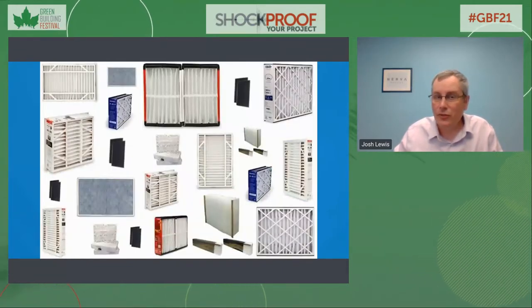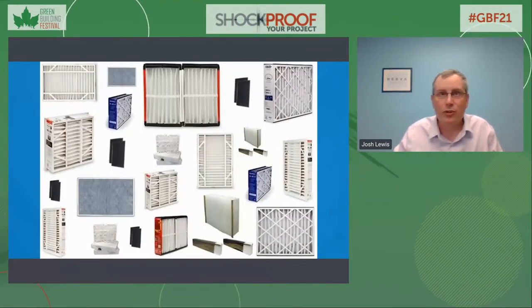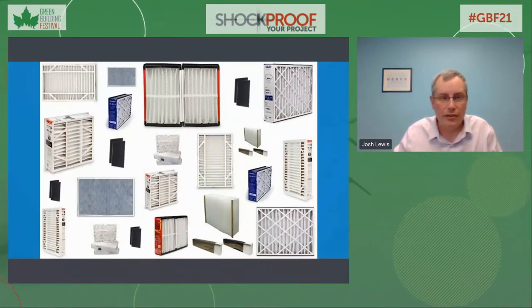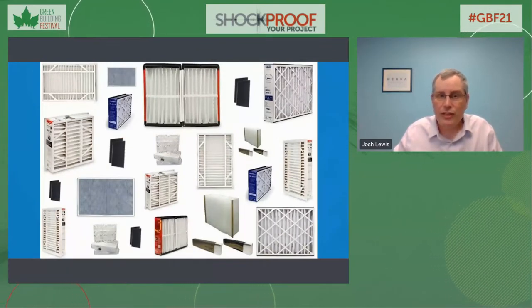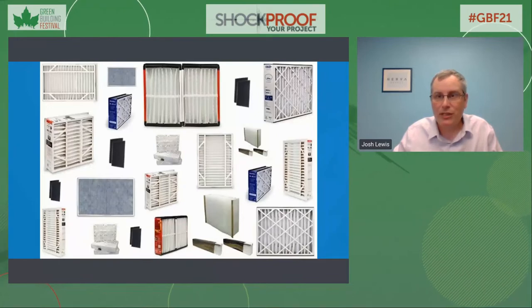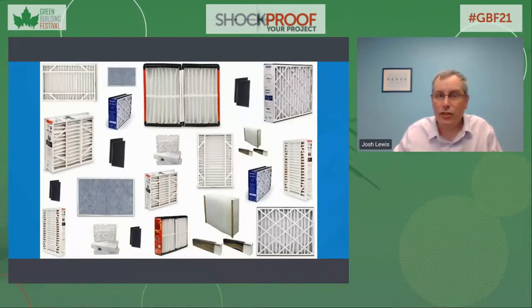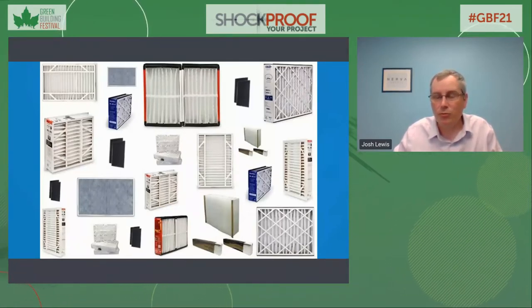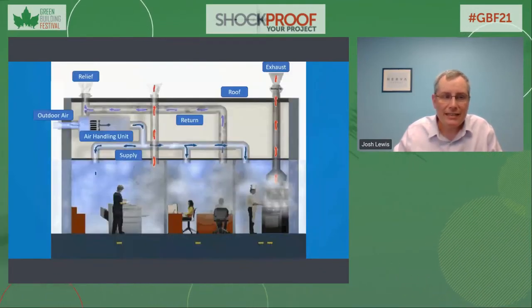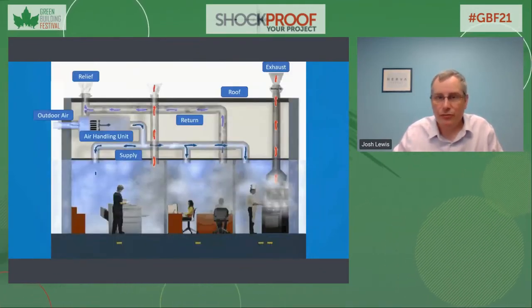In summary, filtration is the first key operational parameter that must be optimized to create a healthy environment. Ensure that the installed filters have the right performance level, that there is a clearly defined strategy to know the current filter condition and when to change them, and that the HVAC system air circulation rates are appropriate for the filters to be effective. The next key operational parameter is dilution.